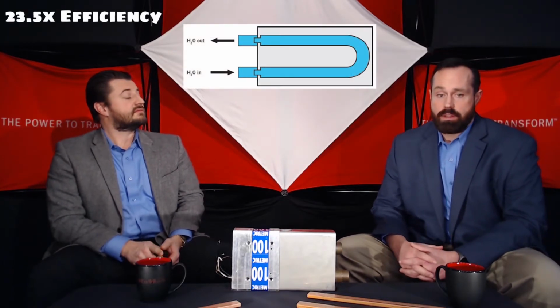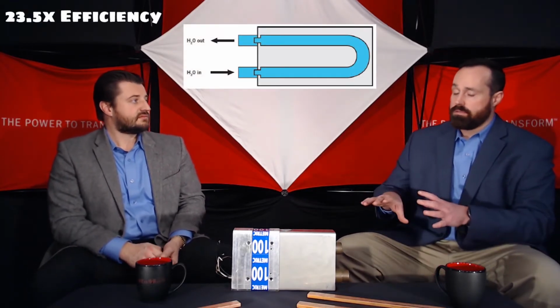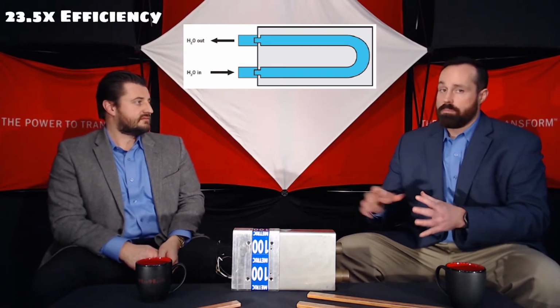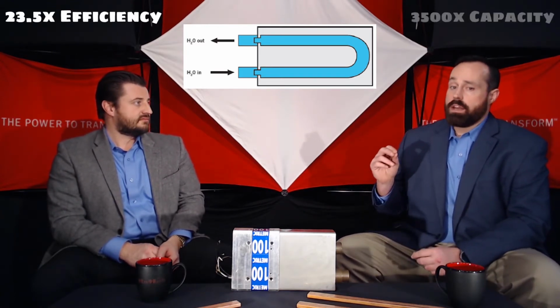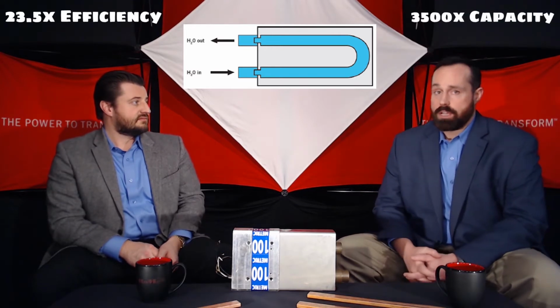So back 40 years ago when RoMan Manufacturing started, why did they choose water as their mechanism of cooling? So the answer is simple. Water is just so much better of a cooling material than air. Water is 23.5 times more efficient at transferring heat than air. And further, given a specific volume of water flow over a component, water has a heat carrying capacity of nearly 3,500 times that of air.